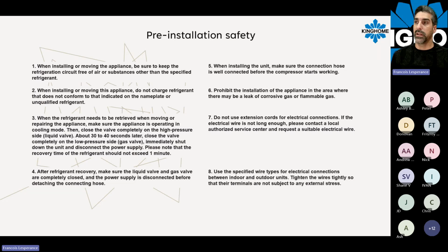And make sure you also check the nameplate on the unit, so that if you have to add more refrigerant to a system, you do not mix refrigerants. Moving forward next year, we will face multiple kinds of refrigerant on the market at the same time. So we will be able to use R410A, and most of the units will be R32, and we will also have R454B available. So this is something you need to pay a little more attention to. Just look at the nameplate, and make sure you are working with the right refrigerant.